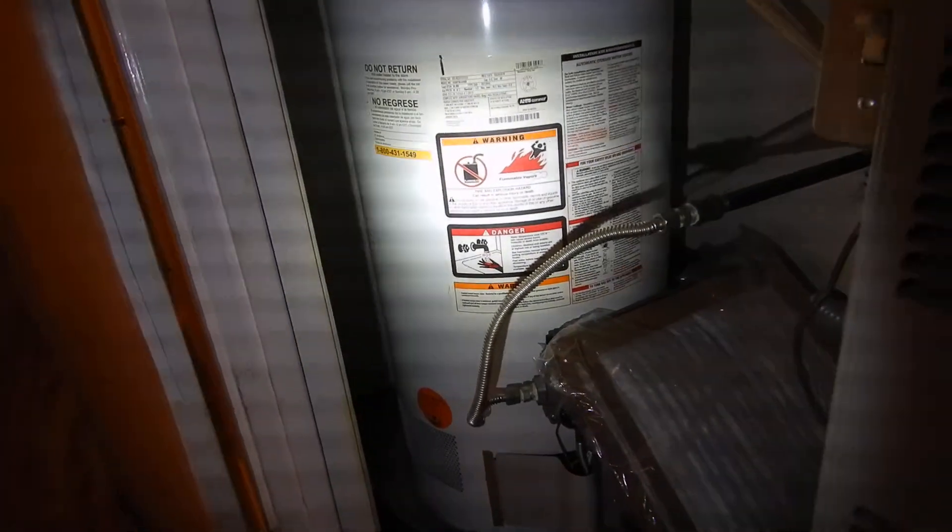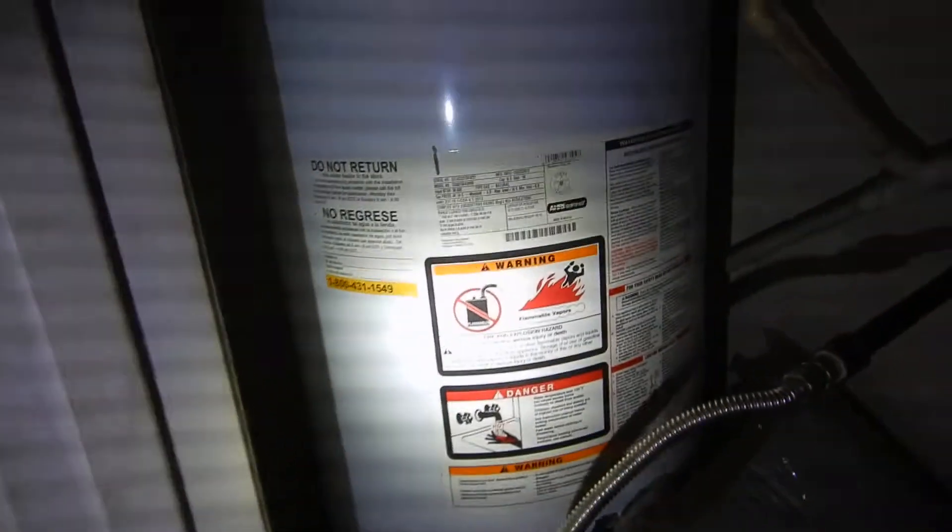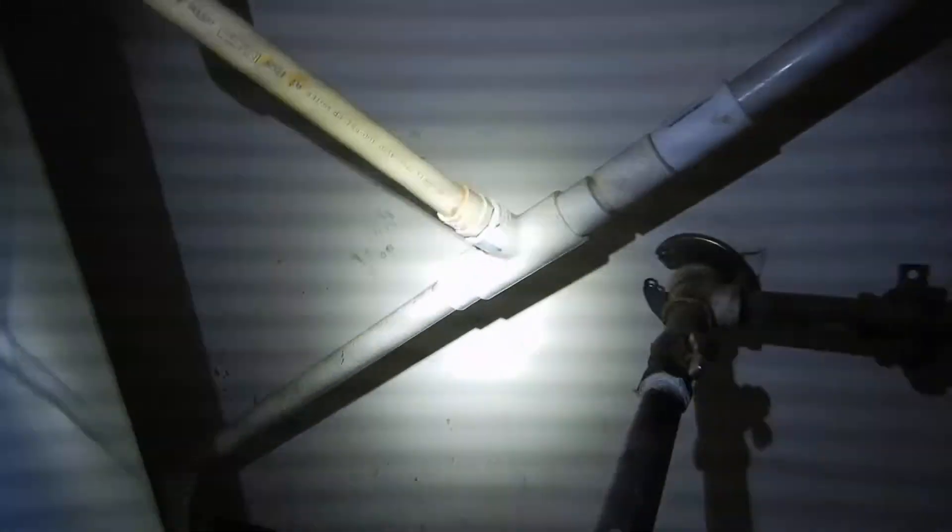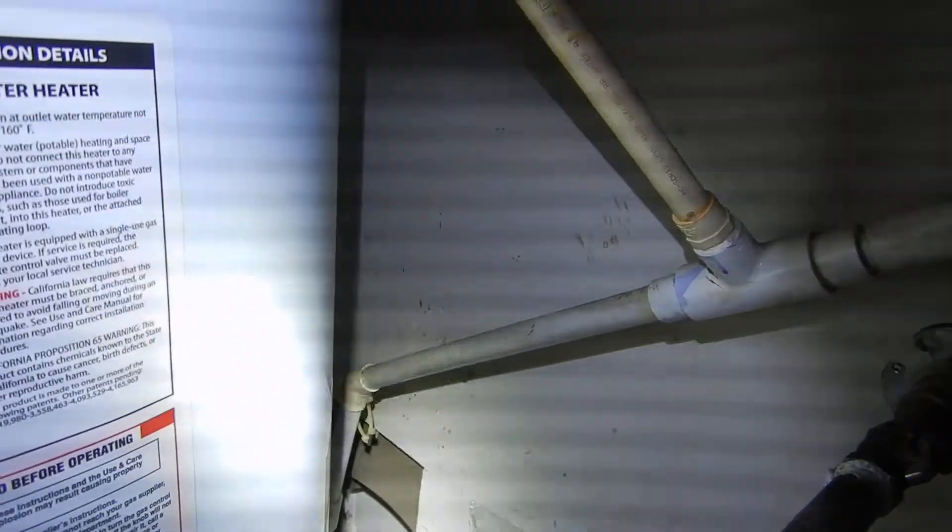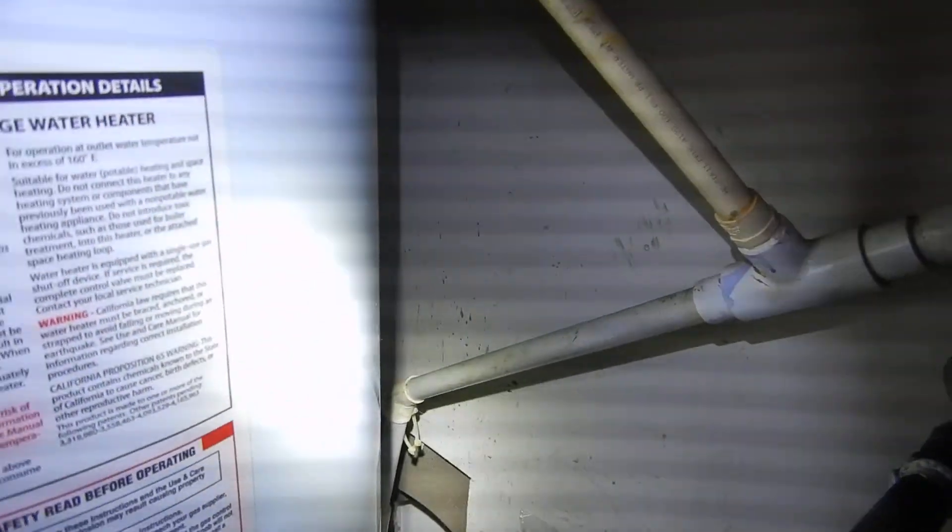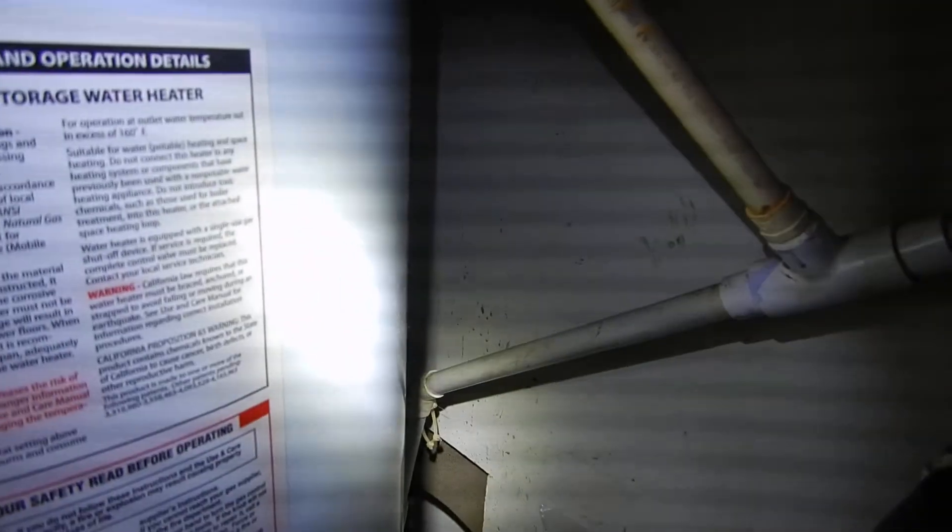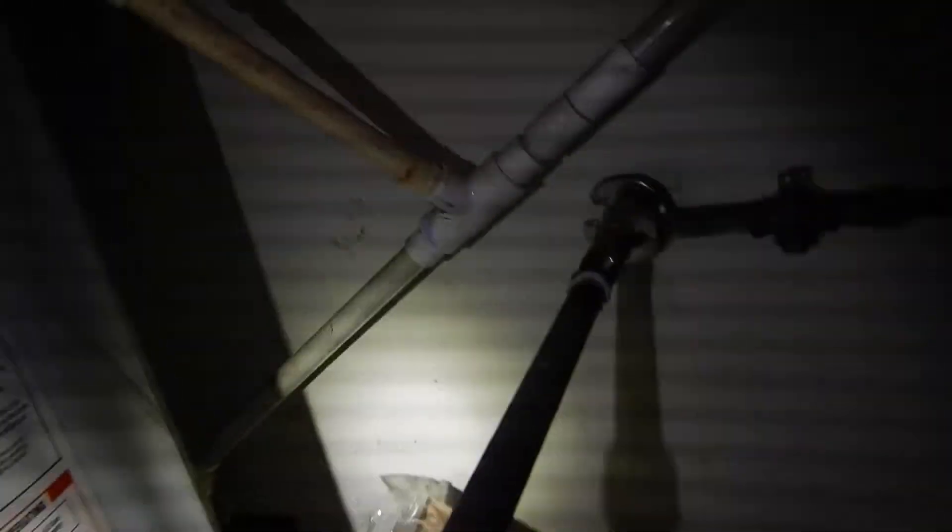Okay, it's 50 gallons and it's in the mechanical closet. Makeup air and the air supply just comes, is what can wick through the closet doors. Oh no, excuse me. We've got a screen down there, and the screen's acceptable down here for our fresh air. So we do have fresh air.